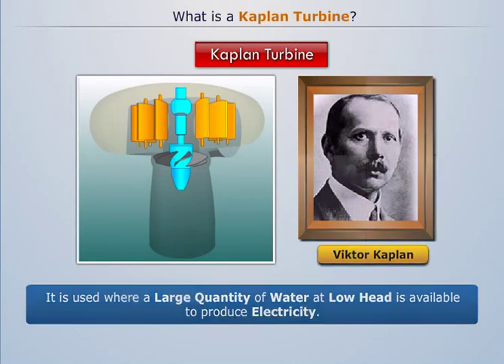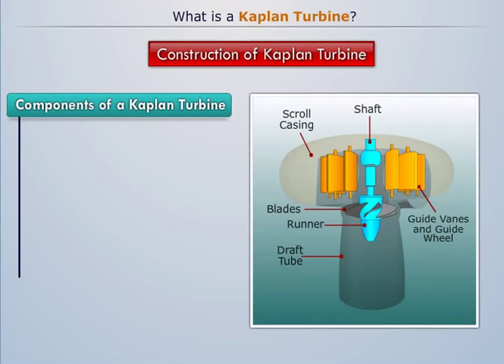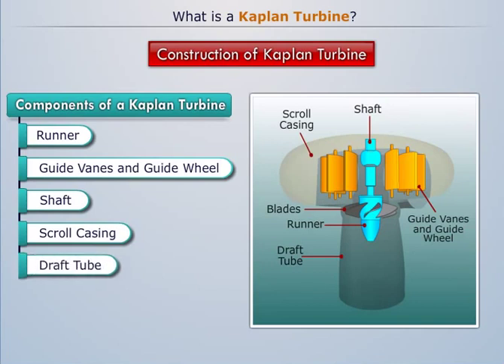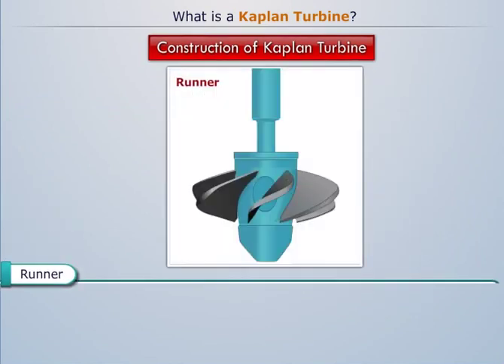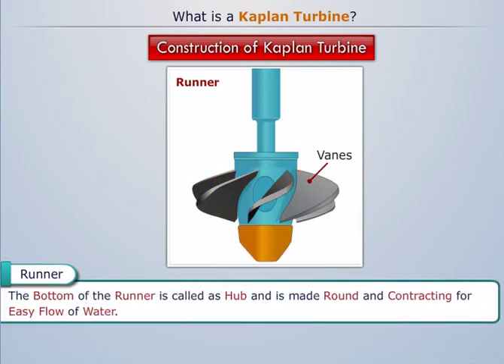Let's first understand the construction of the Kaplan turbine. The components used in the Kaplan turbine are: runner, guide vanes and guide wheel, shaft, scroll casing, and draft tube. The runner is the rotating element of the Kaplan turbine that consists of a number of vanes fixed at its surface. The bottom of the runner is called the hub and is made round and contracting for easy flow of water.